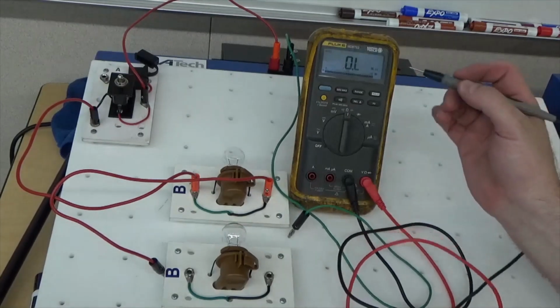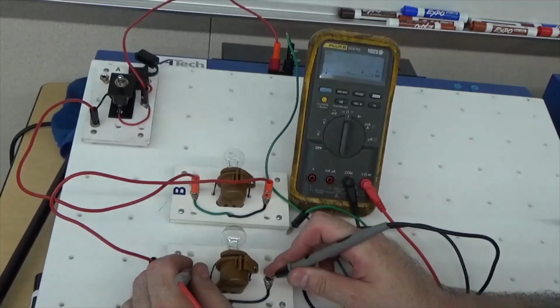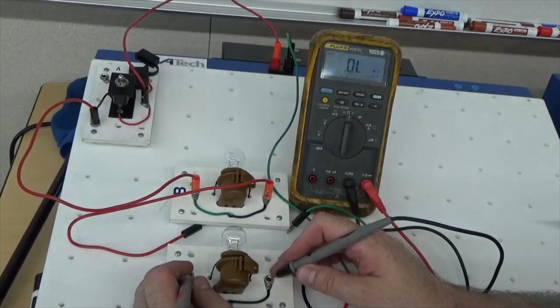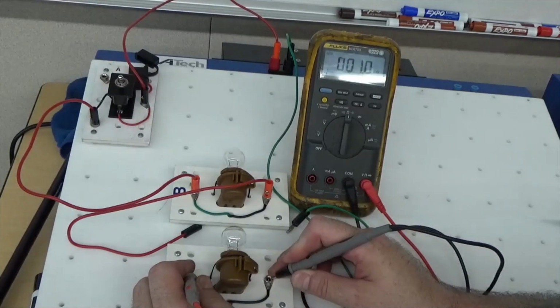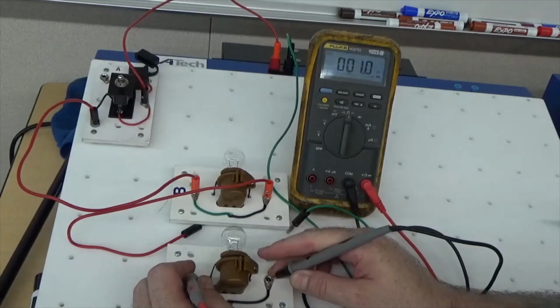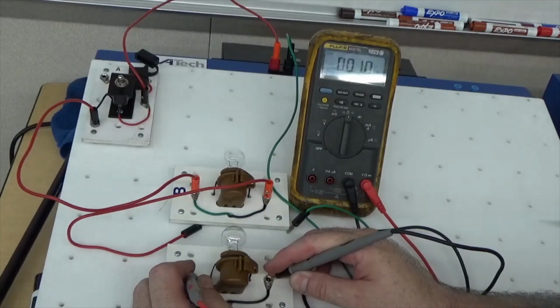So I'm going to measure this resistance. You have ohms right here. I'm going to go here, I'm going to go here. Notice that the part is disconnected from the circuit, okay? The reason is that an ohm meter creates its own private series circuit when it's measuring its values, okay? The meter becomes the power, the protection, and the conducting path, and that lamp is still the load, or whatever it is else you're testing. It doesn't always have to be a lamp. It could be a motor or a solenoid or relay or something like that, okay? And this bulb has got 1 ohm, okay?